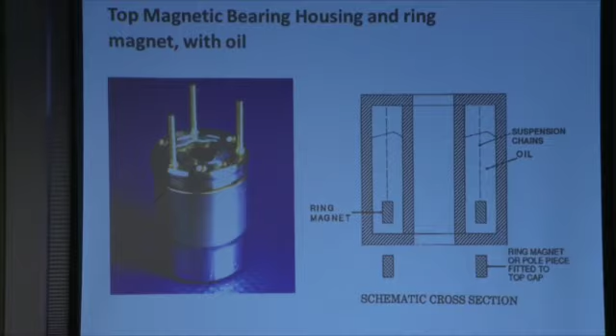Yeah, you can. Well, I showed this picture earlier. You can see them a little better there. The schematic on the right side shows the cutaways of the ring magnet involved in this. The bottom one is just a round ring magnet attached to the top of the centrifuge, and then the top one is in this oil and it's suspended by a little chain in this oil bath. If there's any vibration, the centrifuge can transfer its vibrations to the top ring magnet, and those vibrations are damped out by the oil through dissipation. And that's an actual top bearing housing.